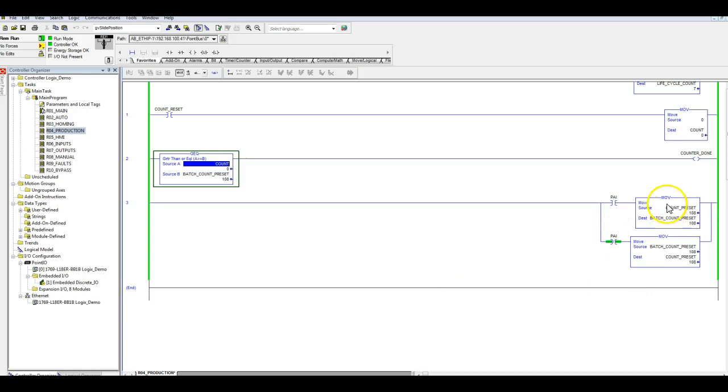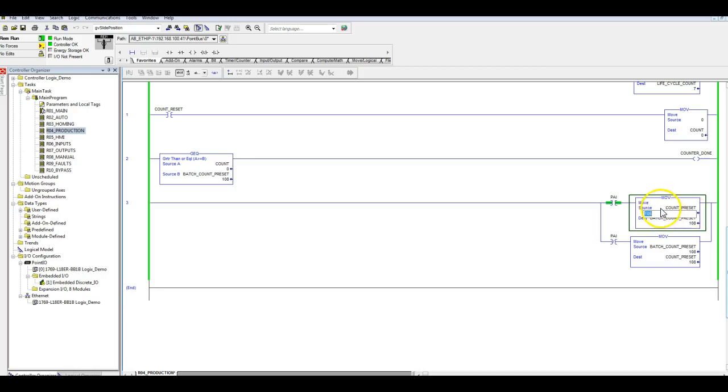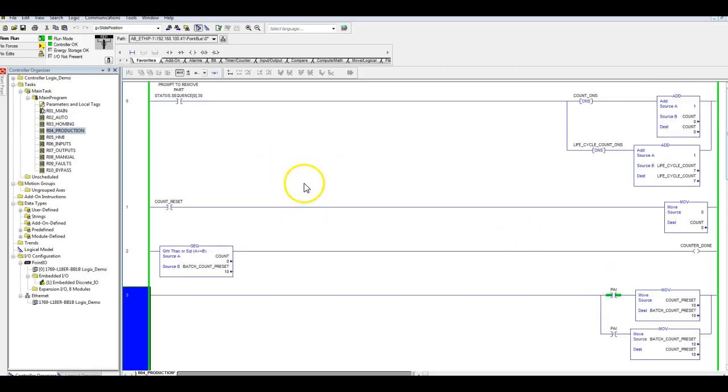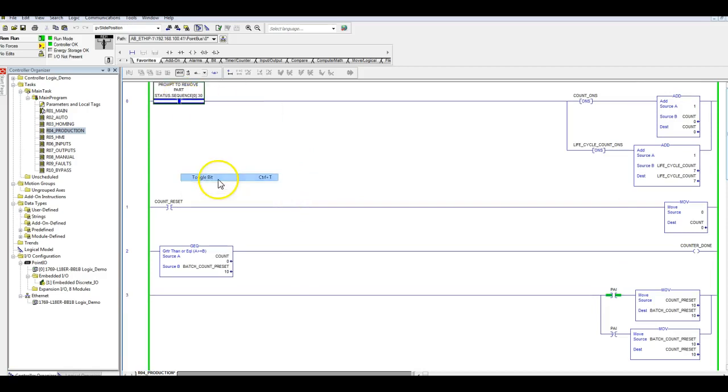It'll get that through this counter done bit right here. To change the preset, this is a password authorization right here through your HMI, give it permission to set what the preset is. If I toggle this bit that's going to give me the ability to count preset. I can put this in batches, make this 10 if I so choose.